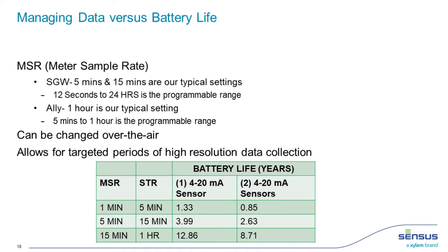Same sort of thing with an Ally meter - our Ally meters read pressure data at hourly resolution. With the smart gateway, we're able to lower that meter sample rate anywhere from 12-second samples to 24 hours, and it's programmable over the air, so it can be changed. If you need more data for a short amount of time, you can increase that sample rate and collect data for a week or two, then change it back to preserve battery life. It's really a minimal infrastructure investment to monitor your entire distribution system.